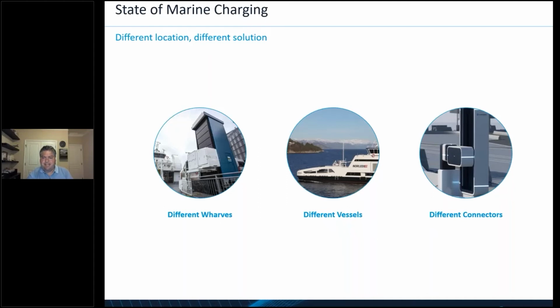And then, of course, the last piece is the different connections. Whenever you would have a different power level, you would be asking for a different connector size to connect to the vessel as well. So it could be something from a 600 kilowatt, it could be up to 5 megawatt, right? But the connectors scale quite differently. And also the cables going to the connectors are quite different because of the power level differences. So what happens is it changes both the size of the funnel on the vessel or on the machine. It changes the size of the connector. It changes the size of the structure on the shore side. So there's a lot of variability here from the wharf to the vessel to the connector on what each project looked like. Next slide, please.